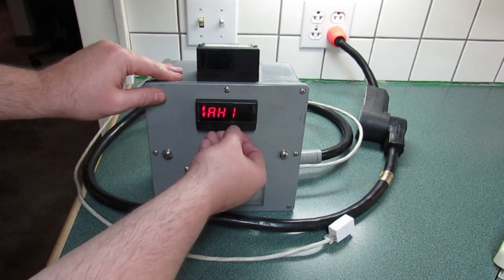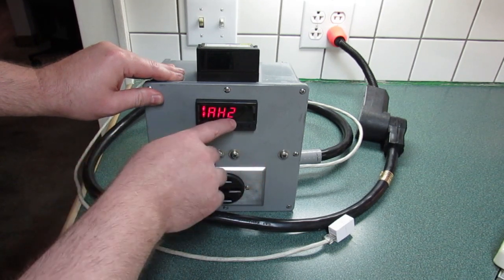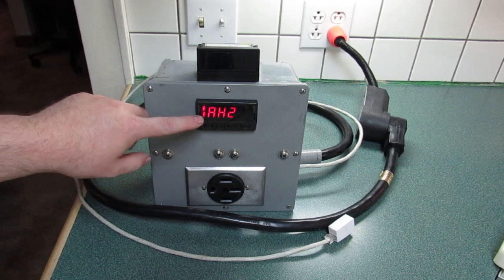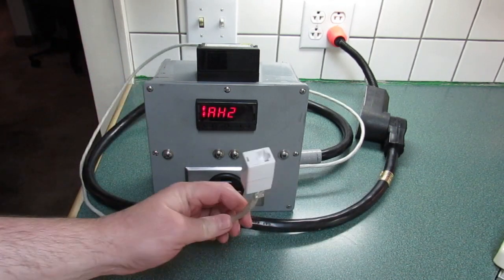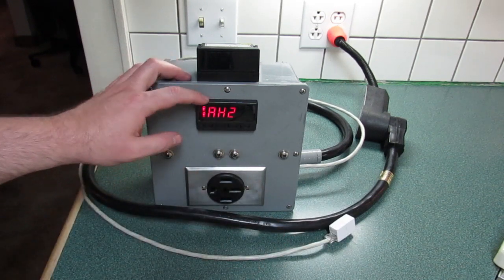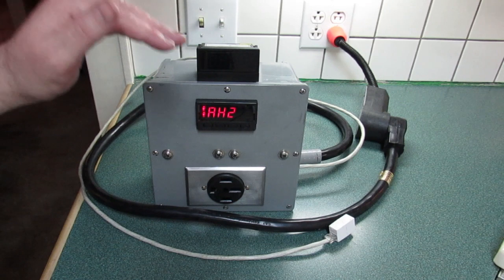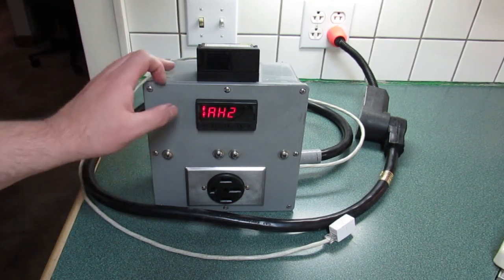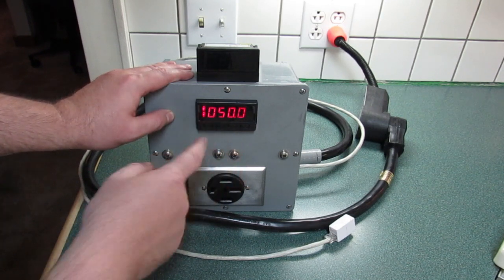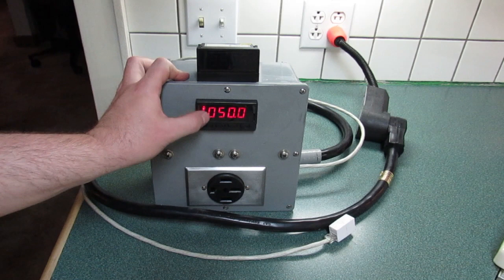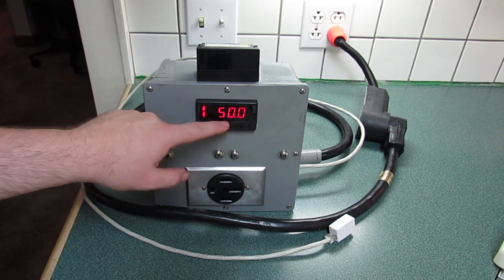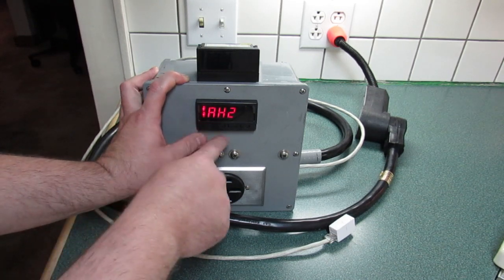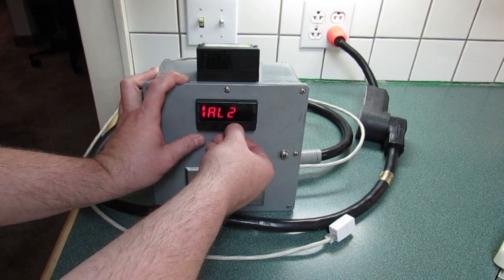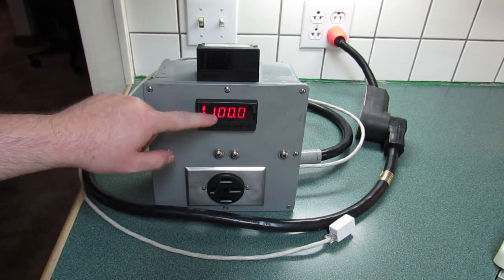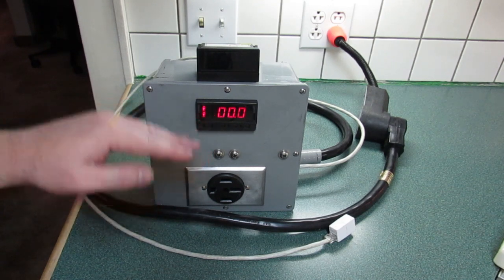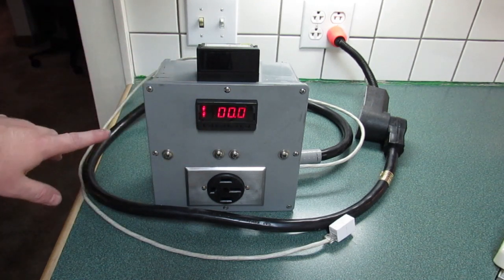So then we have the H2 and L2, which is again for the lower relay. So you'll note that the lower relay is on. Well, the reason why it's on right now is that we have no voltage. There's nothing being fed in here, which means that we are below the minimum voltage that this is set to. And I believe that's H2. We're going to find out here in a second. So 50 volts is what it's set to. So 50 volts is our minimum, at which point it will kick this relay on, and our L2 is our maximum, at which point it will kick this relay off. So if we hit 100 volts or higher, this bottom relay shuts off. And that's what we want.